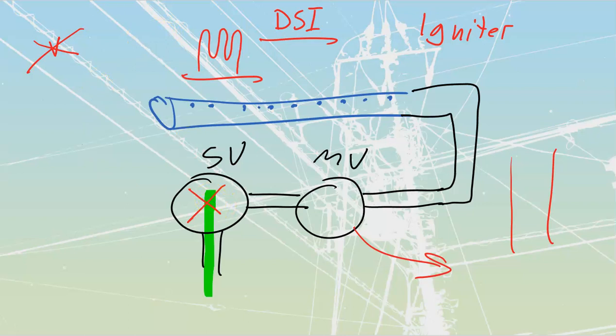It's just going to be inserted into a different section of our controls. So we're just going to put this thing inside here. They usually are long, skinny probes that go over top of multiple gas burners, the actual gas orifices over here. Those flame-proving devices need to be bathed inside of that, and they need to look for heat. They know that initially they're going to be cold. So there's always going to be my signal for the ignition, and then a small amount of timing, and during that time it should be heating up. If at the end of that time, usually no more than a couple of seconds or a second, it does not sense any heat off the igniter, it's going to shut that thing down.